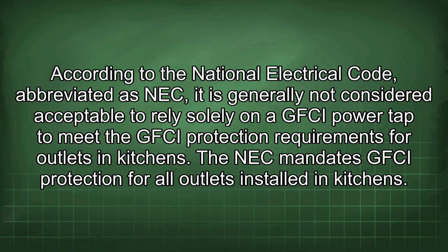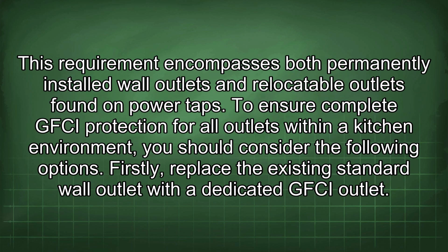According to the National Electrical Code, abbreviated as NEC, it is generally not considered acceptable to rely solely on a GFCI power tap to meet the GFCI protection requirements for outlets in kitchens. The NEC mandates GFCI protection for all outlets installed in kitchens. This requirement encompasses both permanently installed wall outlets and relocatable outlets found on power taps. To ensure complete GFCI protection for all outlets within a kitchen environment, you should consider the following options.